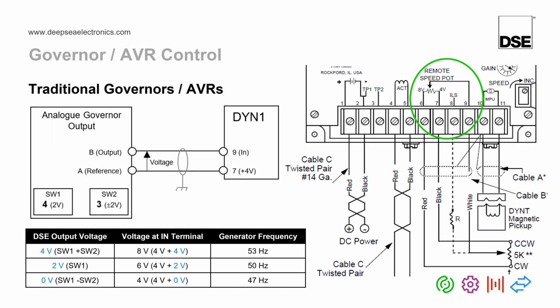Now, the way the DSE module works, however, is it needs to generate a voltage which gets sent to that governor. In this case, for the governor to run at 50 hertz, the DSE module is only generating 2 volts. This is because it's 2 volts added to the 4 volts of this terminal here, which gives 6 volts. And this is actually where the switch 1 value comes in. Switch 1 is how much voltage the DSE module needs to produce to make the generator run at its nominal frequency. So in this case, we have a switch 1 of 4 to run at 2 volts. We produce 2 volts, which gets added to the 4 to make 6 to run at 50 hertz.